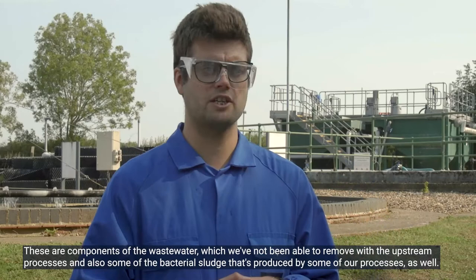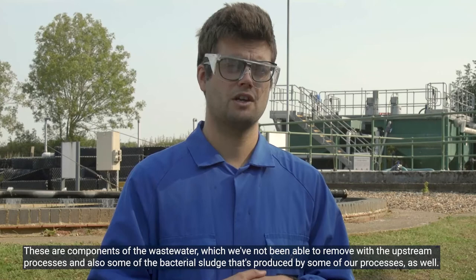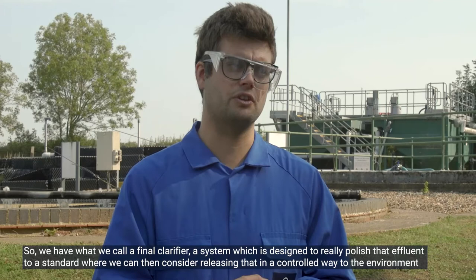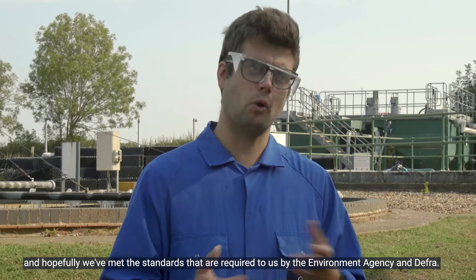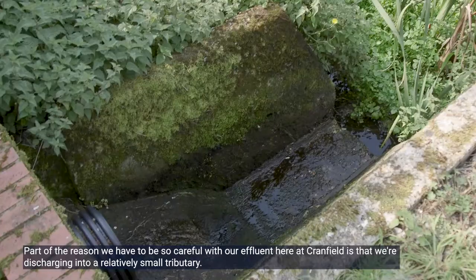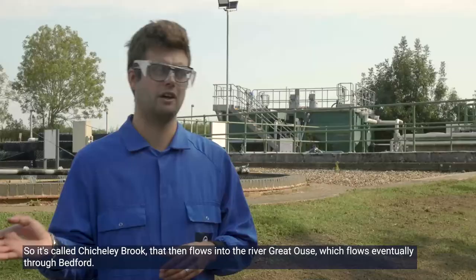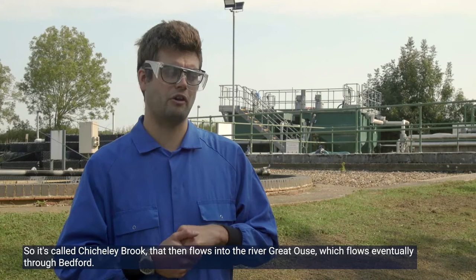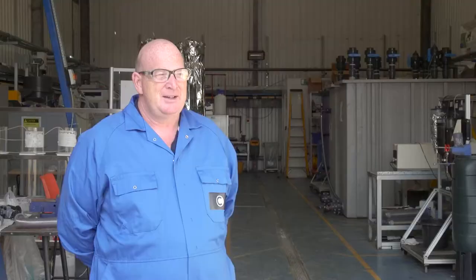...the water still contains a fair amount of what we call total suspended solids — components of the wastewater we haven't been able to remove with upstream processes, plus some bacterial sludge produced by our processes. So we have a final clarifier, a system designed to really polish that effluent to a standard where we can consider releasing it in a controlled way to the environment, hopefully meeting the standards required by the Environment Agency and DEFRA. Part of the reason we have to be so careful is that we're discharging into a relatively small tributary called Chicheley Brook, which flows into the River Great Ouse through Bedford — it's a nitrate-sensitive zone.